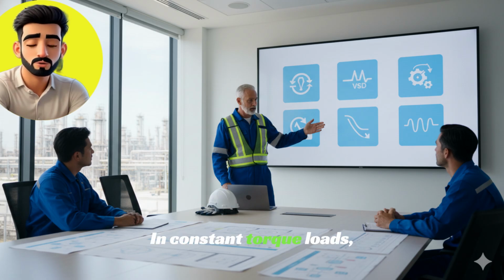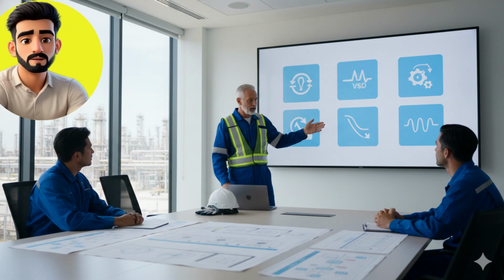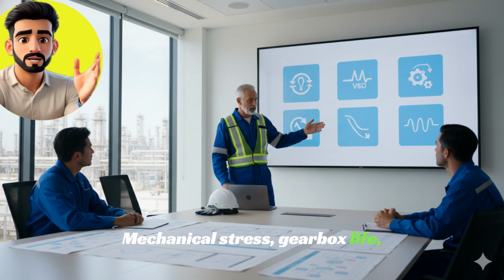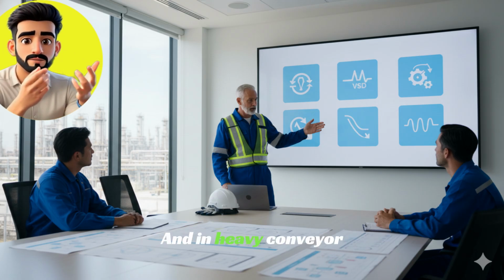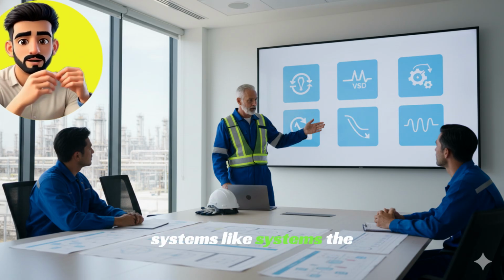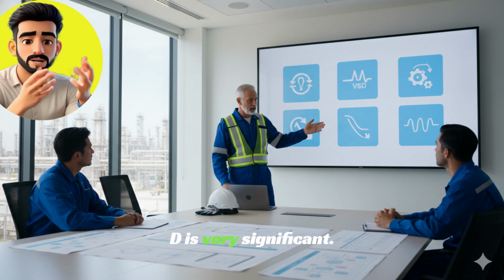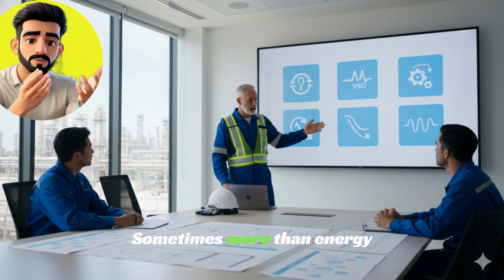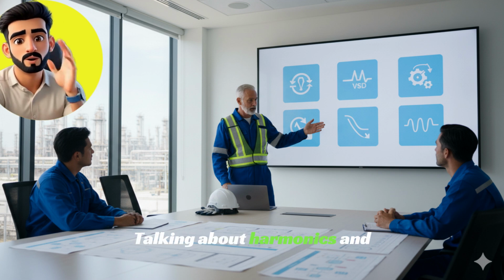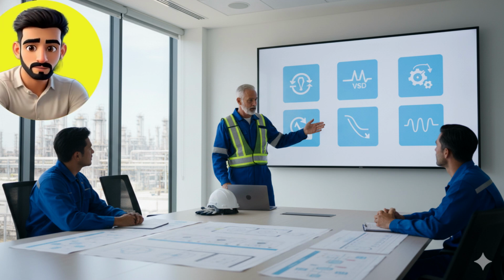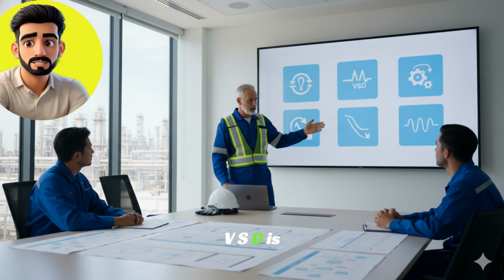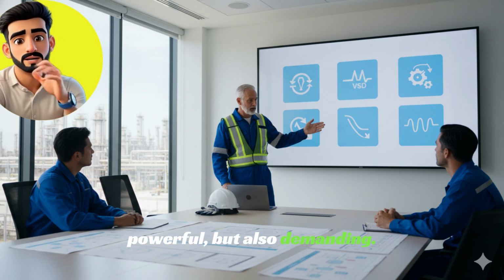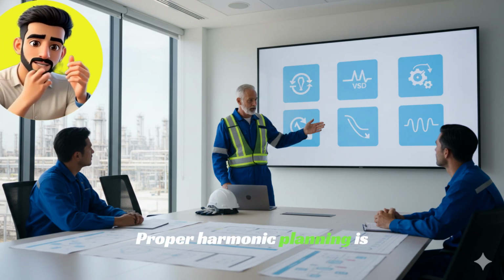In constant torque loads, energy saving is limited. Mechanical stress, gearbox life, pipeline health, and in heavy conveyor systems, the benefit of VSD is very significant, sometimes more than energy saving. Talking about harmonics and power quality, soft starter is clean in steady state. VSD is powerful but also demanding. Proper harmonic planning is essential.